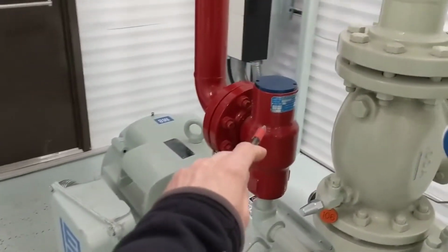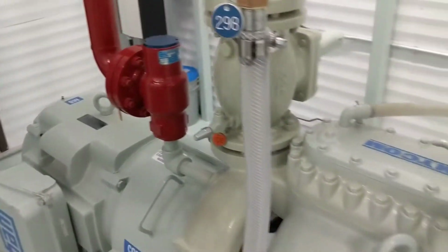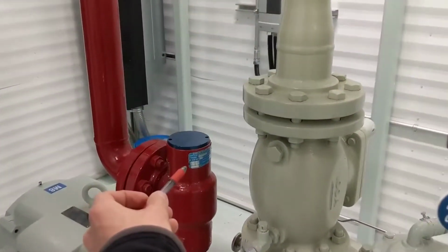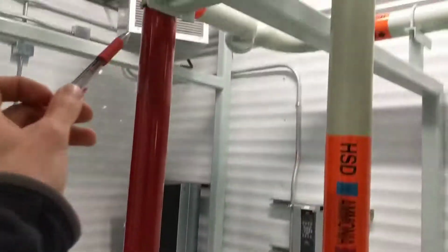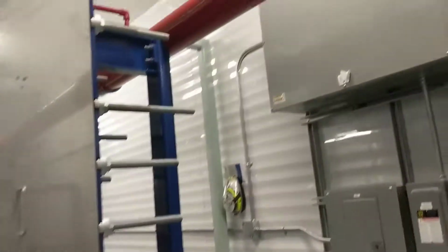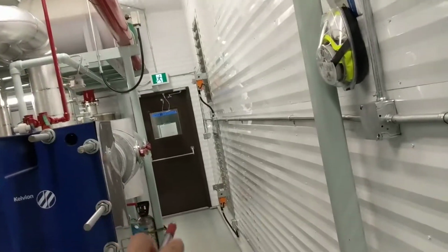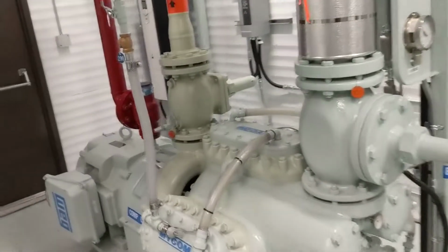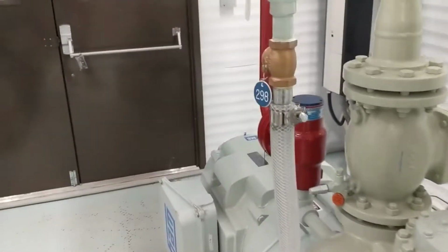Once the ammonia, I should probably also mention, this here is your relief valve. If there was ever to be too much pressure in the compressors for some reason, this would release the ammonia through the relief line, and it would end up over in the corner of the room by going through this and into that water tank down there. That is a great way to have the ammonia contained in water in the event of a high pressure release through a relief valve.